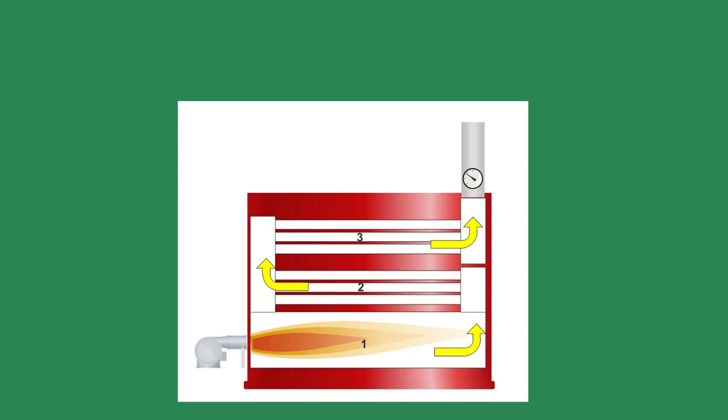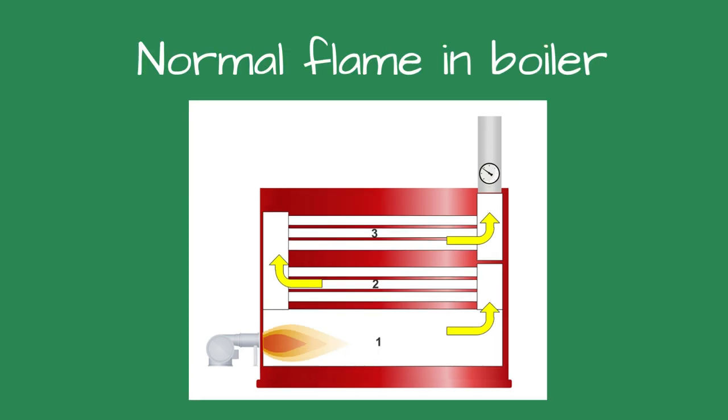It's over-firing, I thought, and connected my manometer to the pressure tap downstream of the gas pressure regulator. The gas pressure reading was within an inch or two of the rated pressure.